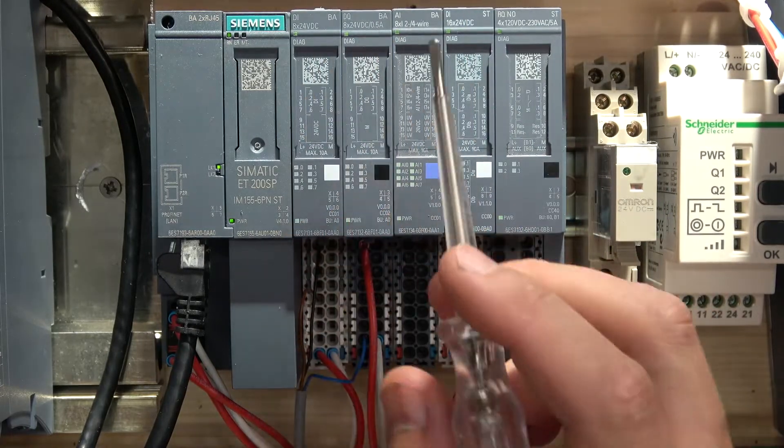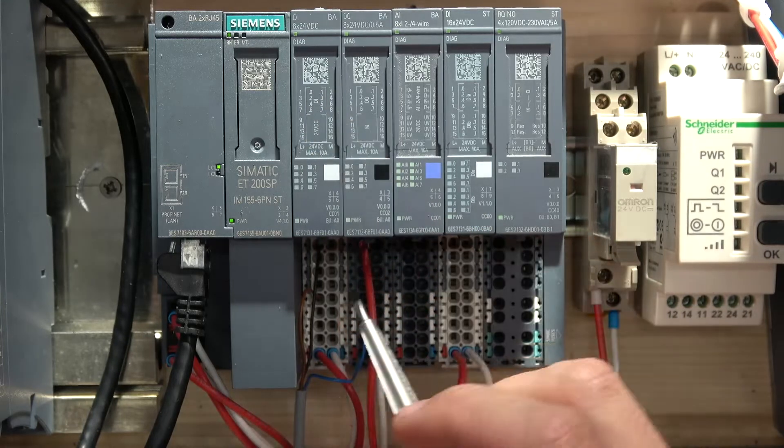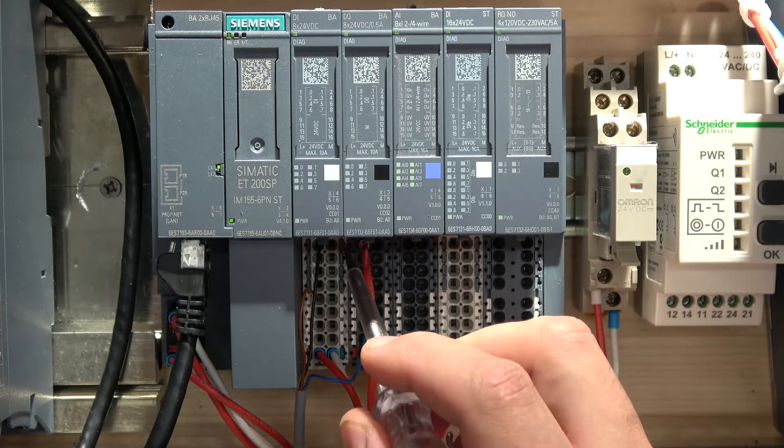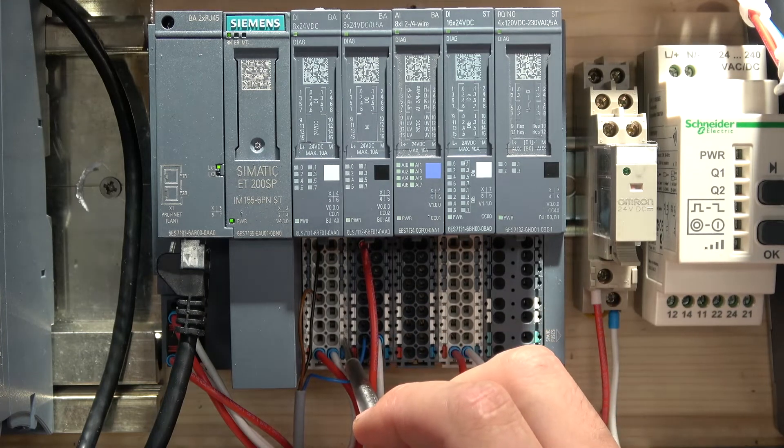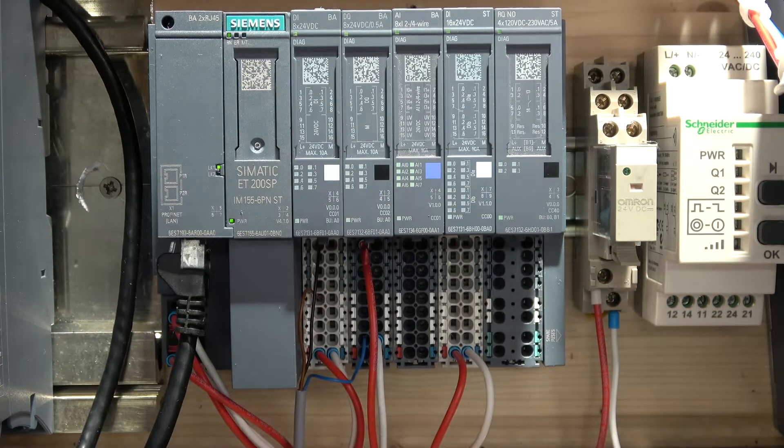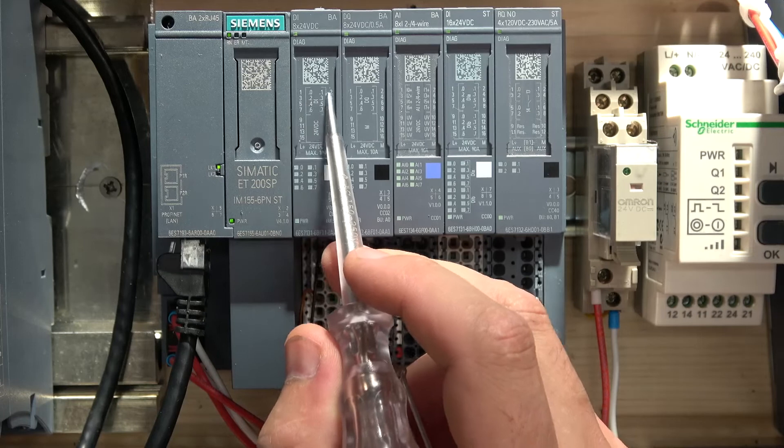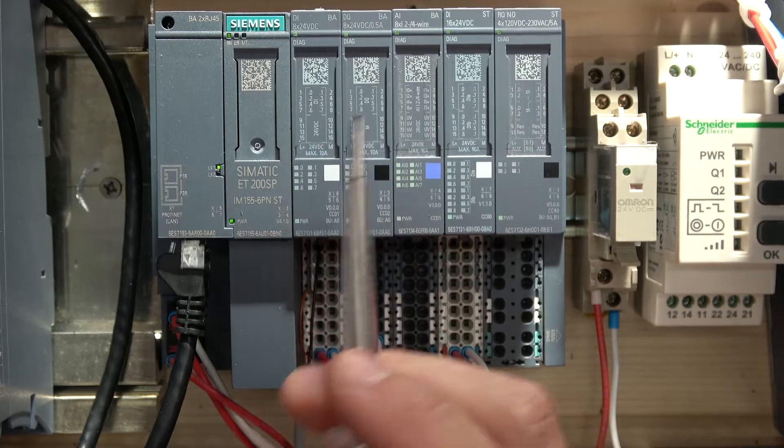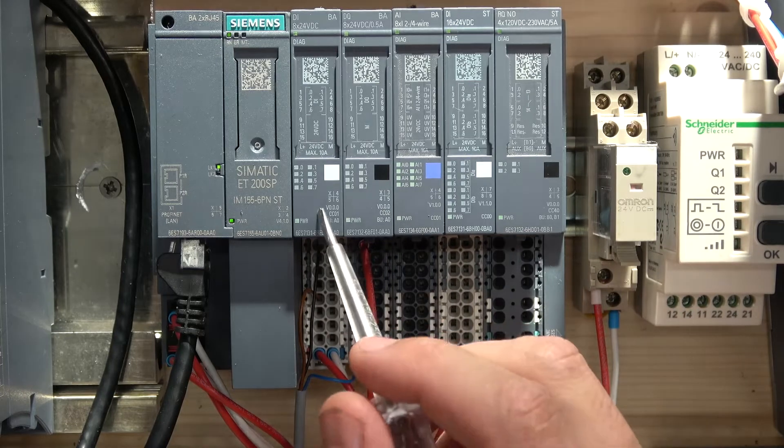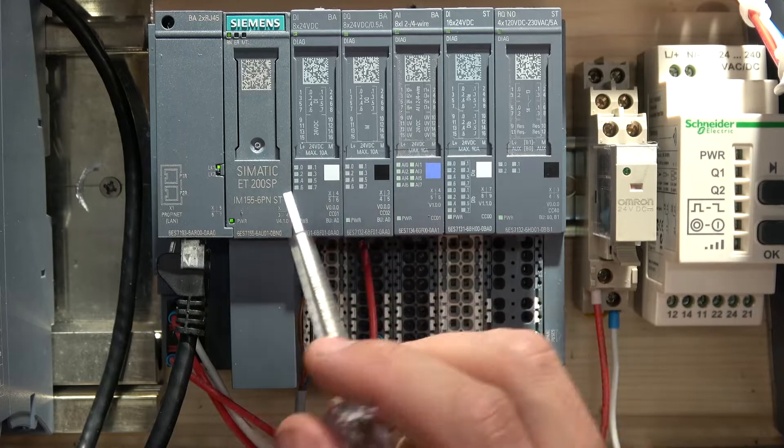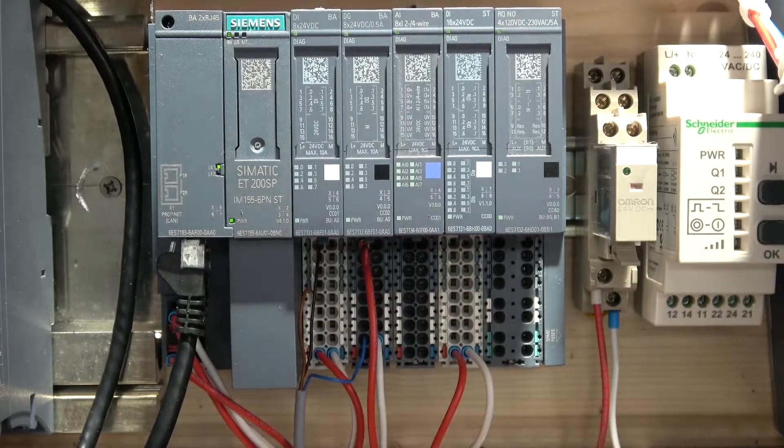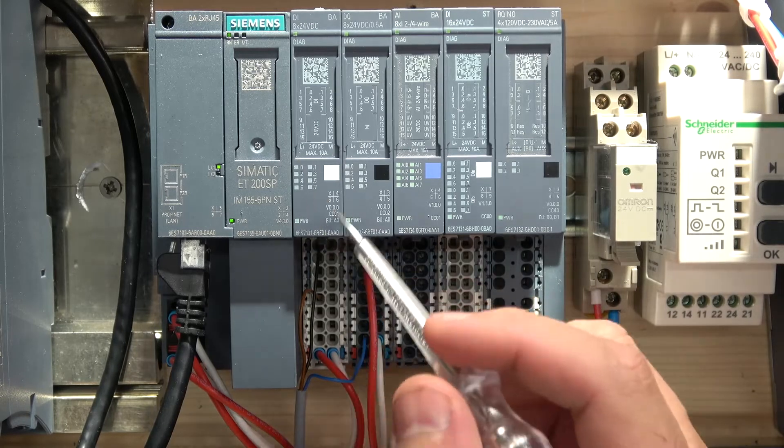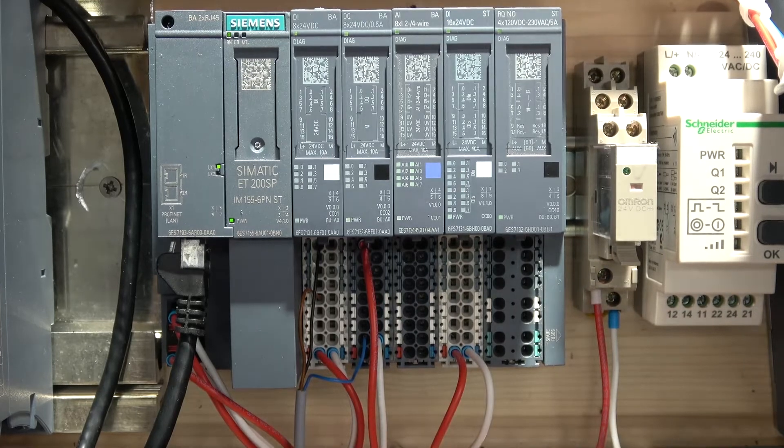Pay attention to this window in here. We have two sections in the base unit. Section one is light gray and section two is white. As you can see, this is eight times 24V DC and it says it's using only one section. So zero to seven bits are for this particular card. And as you can see, another bank says you can use the other bank for your 24 volt outputs if you wish to do so. In my case, this is used as 24 volt outputs.